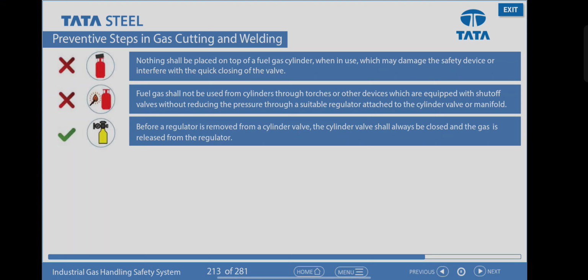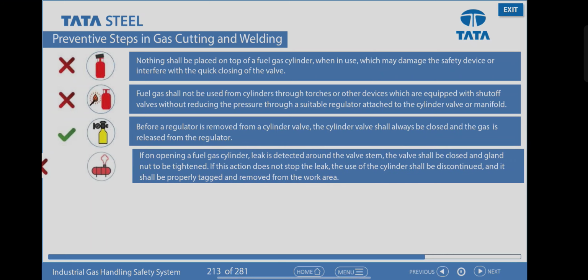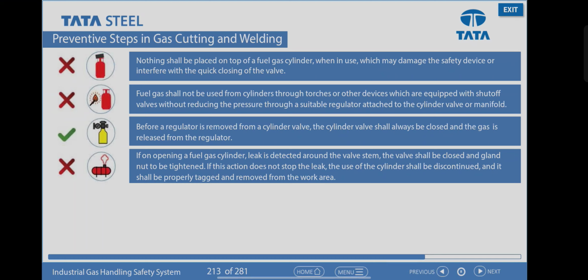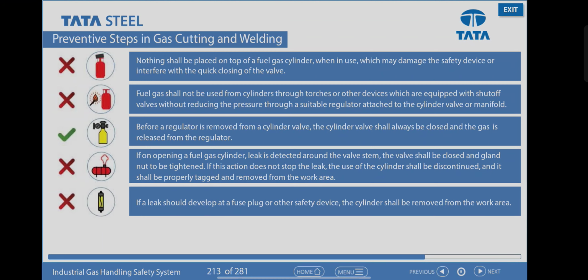Before a regulator is removed from a cylinder valve, the cylinder valve shall always be closed and the gas released from the regulator. If on opening a fuel gas cylinder, a leak is detected around the valve stem, the valve shall be closed and the gland nut tightened. If this action does not stop the leak, the use of the cylinder shall be discontinued and it shall be properly tagged and removed from the work area. If a leak should develop at a fuse plug or other safety device, the cylinder shall be removed from the work area.